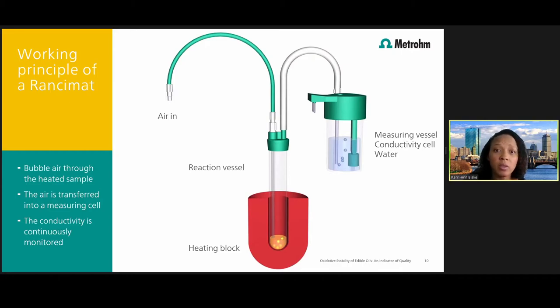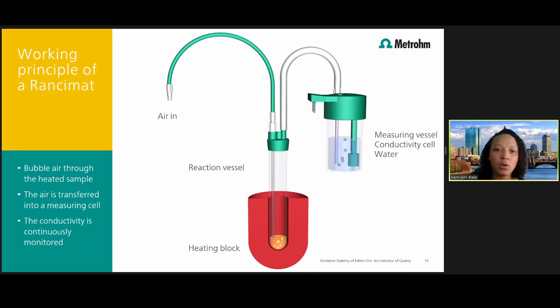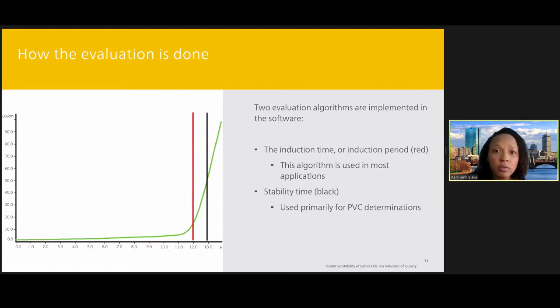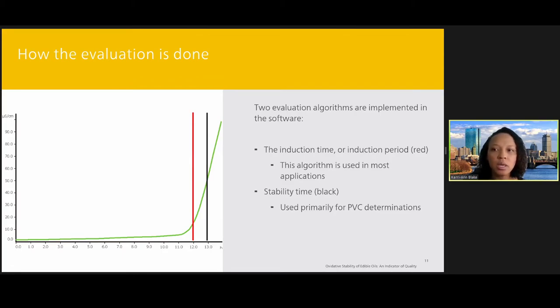The conductivity of the water is continuously recorded throughout the measurement. As soon as volatile carboxylic acids are formed in the sample, it causes an increase in conductivity in the measuring vessel. The time until the secondary oxidation products occur is called the induction time, and this is a measure of the oxidative stability of the sample. There are two evaluation algorithms used by the software: induction time, or induction period, which is used in food applications; and stability time, which is the time until a defined conductivity stage has been achieved and is usually used for PVC determinations involving thermal stability. For this talk, we will focus on induction time.